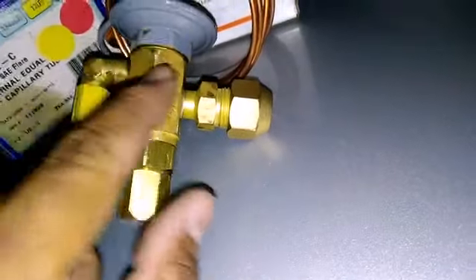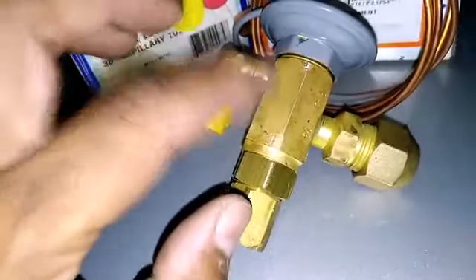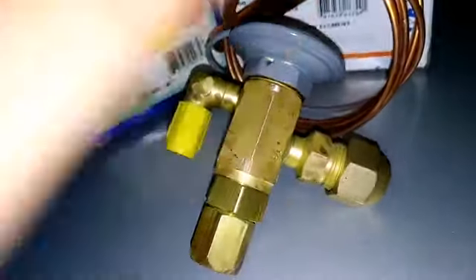This one is basic — as you can see inside, it's just a cartridge with a spring in it. This other one has two rods in it, so you could take the guts out and change them if you had to. Sometimes the guts just get dirty, so you take the whole thing apart, clean the guts out, take the power head off, and clean the rods.